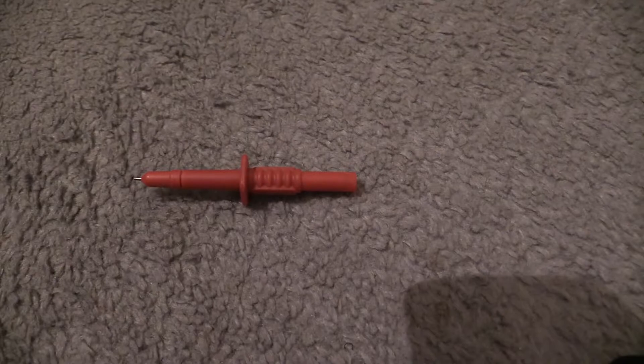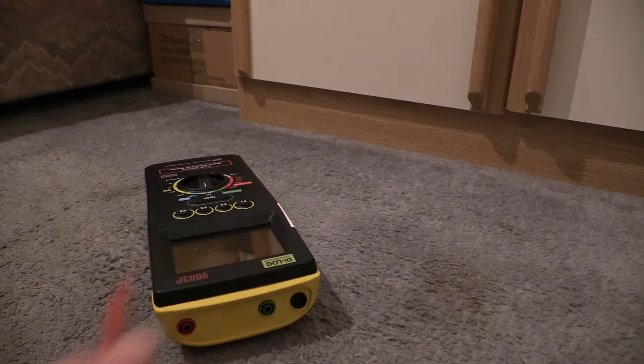Yeah, 300 volts, category 3. So like I say, that little stumpy probe connects into the top of the tester. The idea being, when you're trying to hold that tester and carry out the test at the same time, it's pretty obvious we've only got two hands. So you'd put this test probe in that red hole there, connect that in, and then the test equipment becomes a test probe.